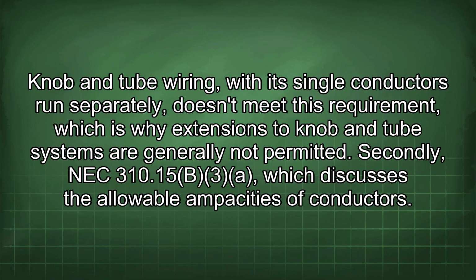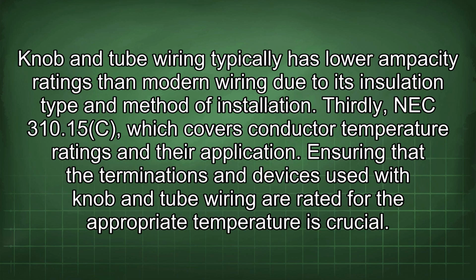Secondly, NEC 310.15(B)(3), which discusses the allowable ampacities of conductors. Knob and tube wiring typically has lower ampacity ratings than modern wiring due to its insulation type and method of installation. Thirdly, NEC 310.15(C), which covers conductor temperature ratings and their application. Ensuring that the terminations and devices used with knob and tube wiring are rated for the appropriate temperature is crucial.